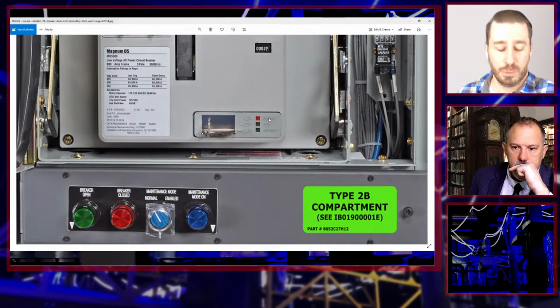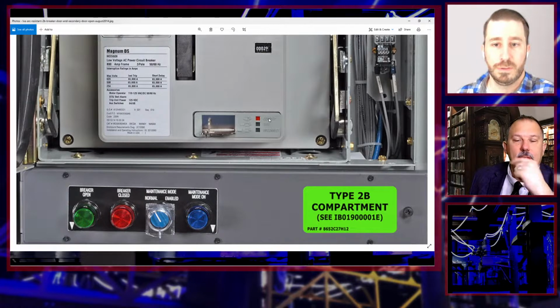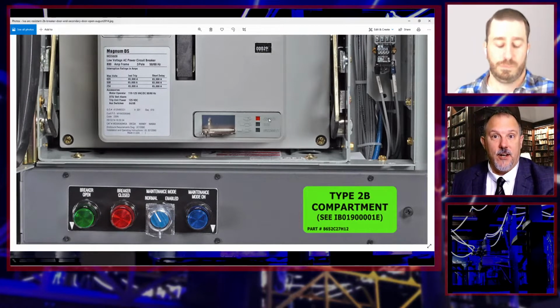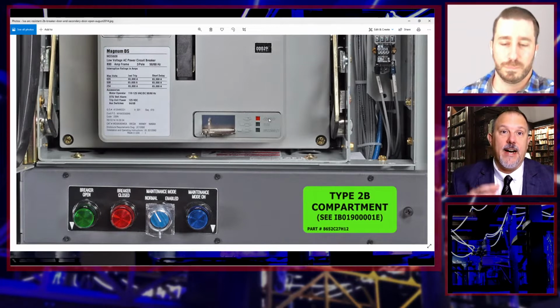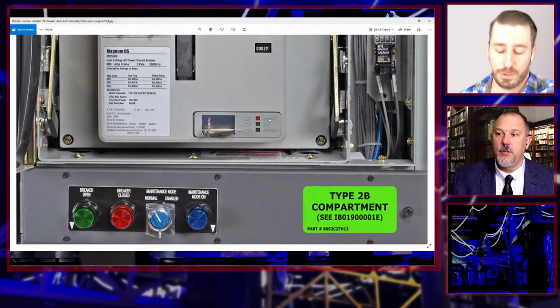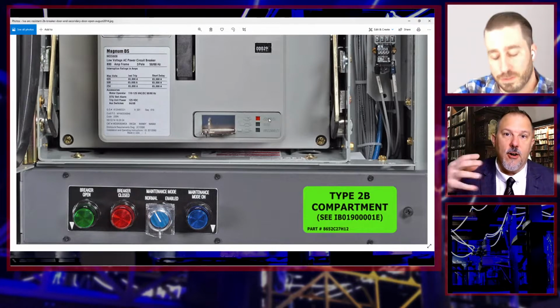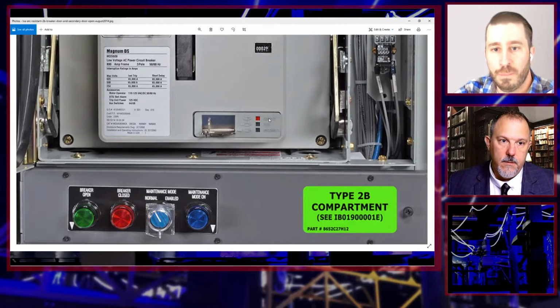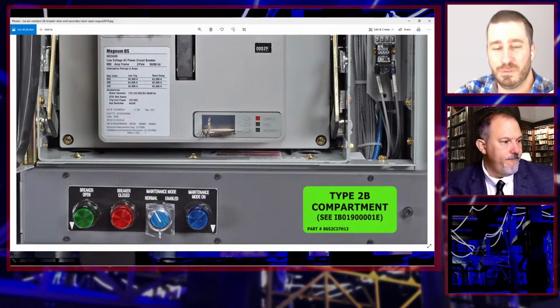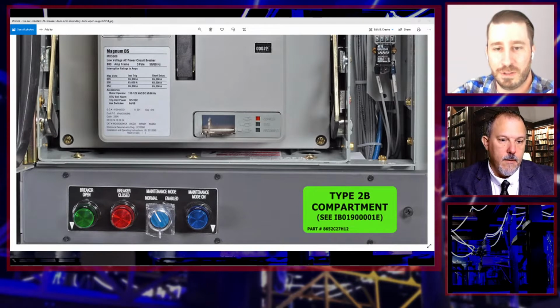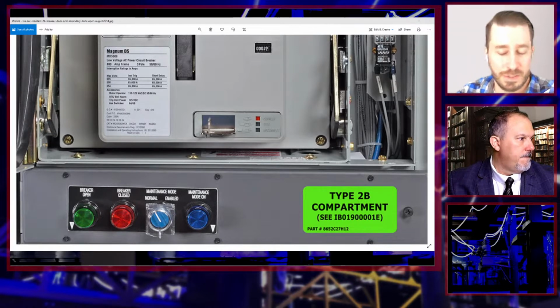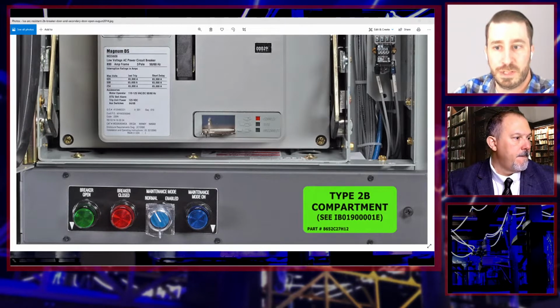If you could achieve faster clearing time from quicker interruption of an arcing fault, you might achieve the same arc resistant rating using standard equipment. That's a good point, like with arc quenching technologies. If I have an arc quencher in there, I might be able to change my construction a bit, because the arc quencher takes care of the energy and forces. Think of the design as really being a symptom of how a manufacturer had to deal with that type of energy buildup. A lot of designs can vary, but these are common attributes you see, though they don't always apply.